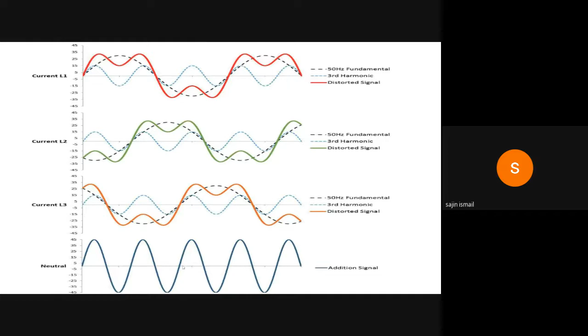With the generation of more triplen harmonics in all three phases, when you add them together, the neutral current will be I1 plus I2 plus I3. As we know, it should normally be 0, but what happens is it will add up if this harmonic content is not taken care of. The additional current will form in the neutral. This neutral current will cause a lot of issues. It will be a huge current created by the triplen harmonics if we are not addressing the harmonics.